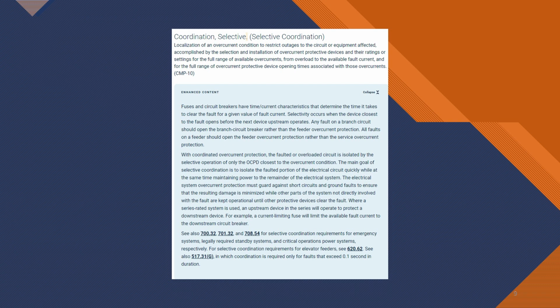To add to the confusion of what selective coordination is, this definition can make your eyes glaze over unless you're really adept at this. It's kind of a mouthful. Localization of an overcurrent condition to restrict outages to the circuit or equipment affected, accomplished by the selection and installation of overcurrent protection devices and their ratings or settings for the full range of available overcurrents from overload to the available fault current, and for the full range of overcurrent protection device opening times associated with those overcurrents. Right?